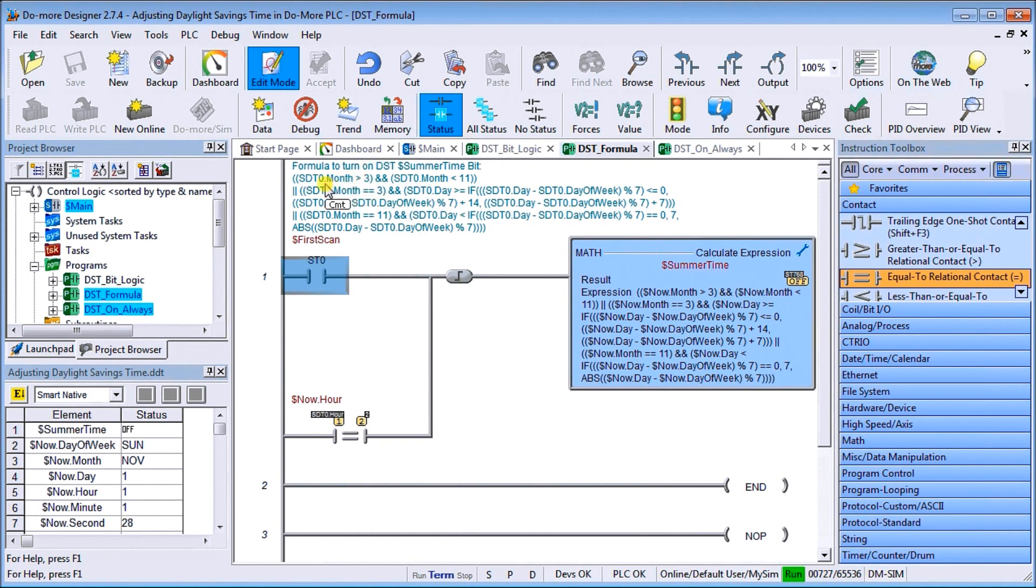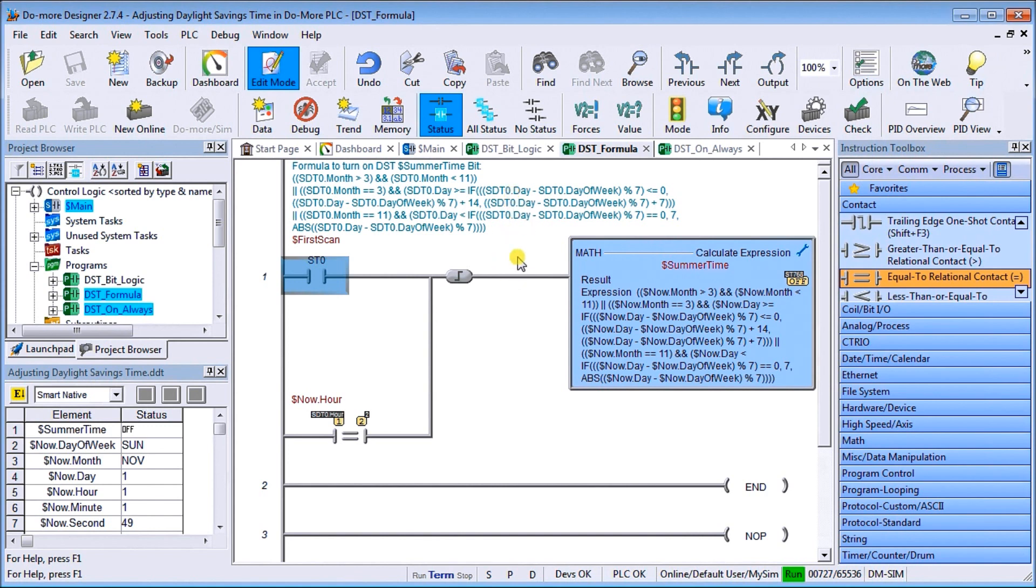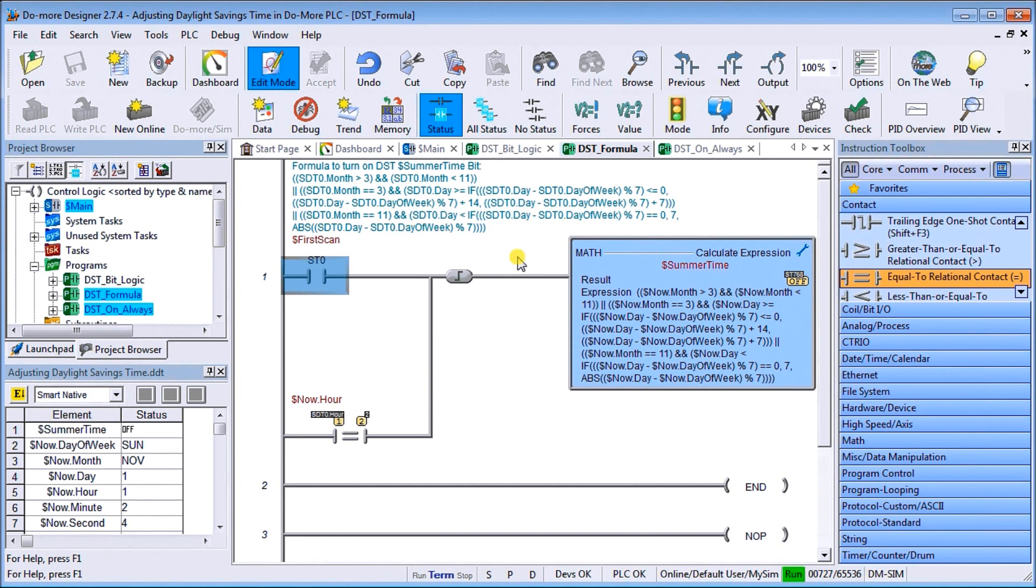We'll call that up. So here's the formula, it looks quite complicated but it's really quite straightforward. What we have is our month. If it's greater than three or less than 11, then what we do is we turn on our summertime bit. Then if it is equal to three, there's a bunch where they have said it has to be greater than the day of seven, or it has to be equal to Sunday, and it has to be within the second week to actually turn that summertime bit on. And it has to be then less than two when it goes off in November and the first Sunday.